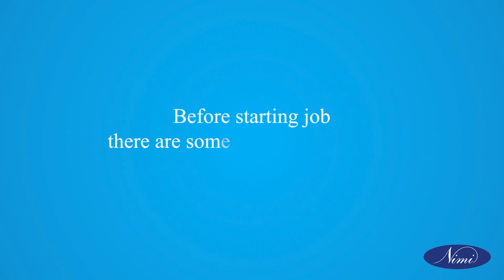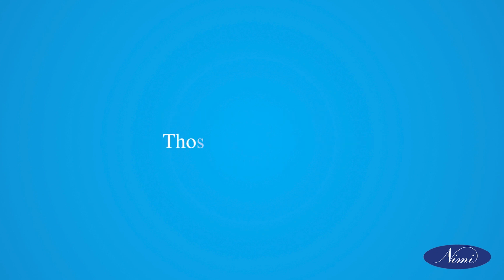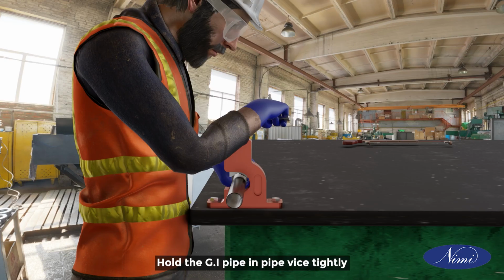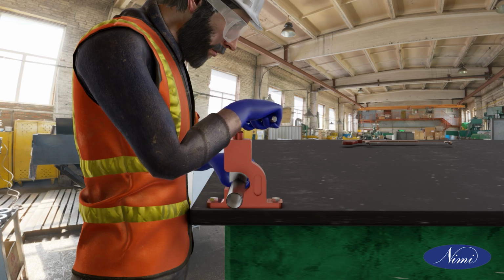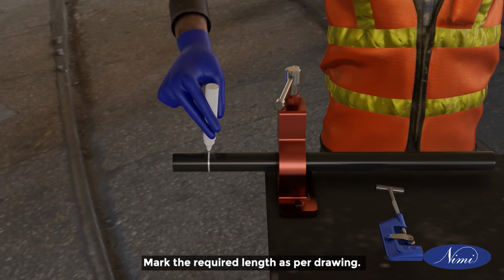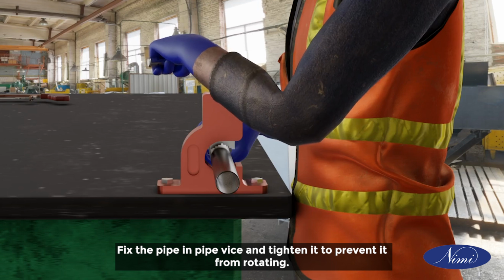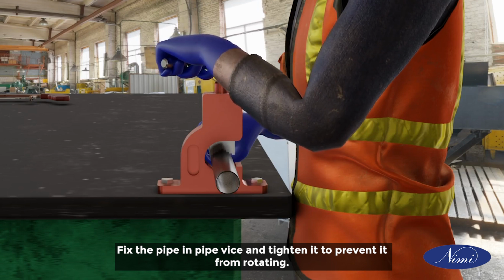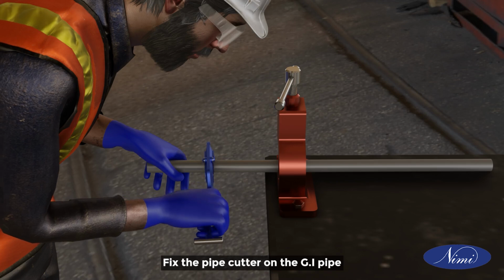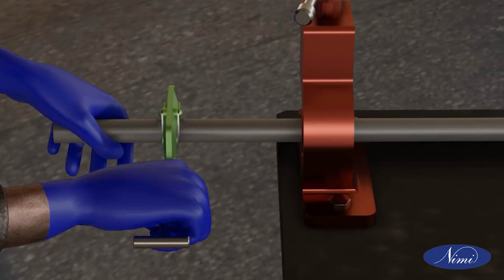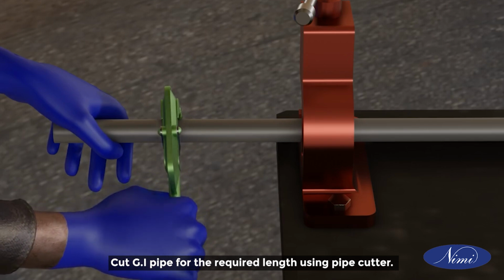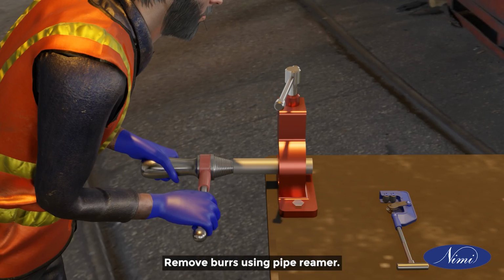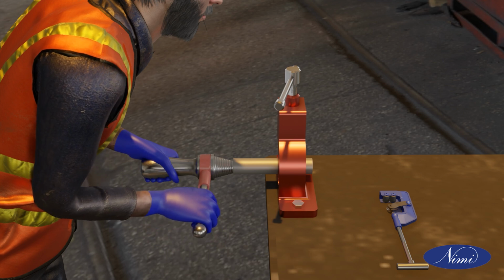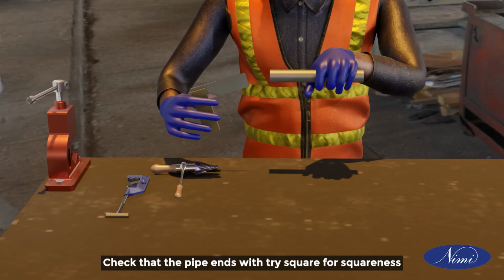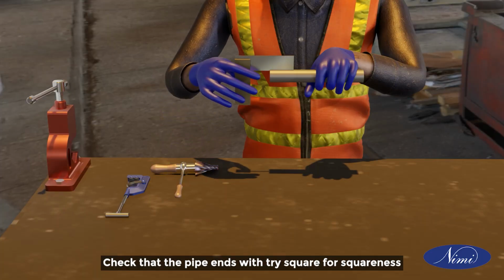Before starting job, there are some preliminary checks to be made. Those are as follows. Hold the GI pipe in pipe vise tightly. Mark the required length as per drawing. Fix the pipe in pipe vise and tighten it to prevent it from rotating. Fix the pipe cutter on the GI pipe. Cut GI pipe for the required length using pipe cutter. Remove burrs using pipe reamer. Check that the pipe ends with try square for squareness.